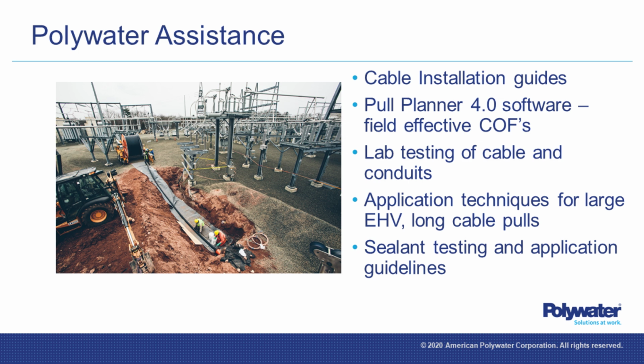If you go to the maximum pulling tension, shouldn't consideration be given for the ability to remove the cable without lubrication? That must be taken into consideration versus pulling to the maximum calculated pull distance. So in other words, this comes from a utility, if you max out on the pulling tension when the cable goes in, how does that impact you if you have to remove the cable later?